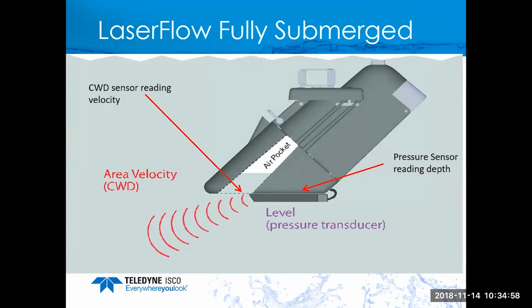The way the AV sensor is mounted on this, we are now going to be looking in the right location for that velocity. So the results when it transitions over from laser to the area velocity have been really, really very, very impressive. Also, it should be noted that we can store one flow rate that will automatically switch from laser to the AV sensor during this condition. So when you graph your data or you send it 4 to 20 to a SCADA, you'll have one continuous flow reading that will be representative of whichever technology you decided to use.